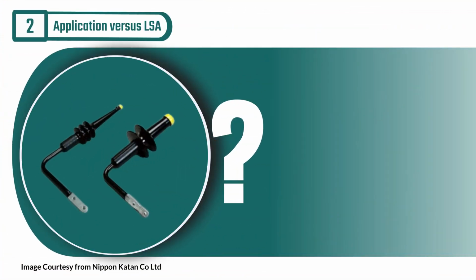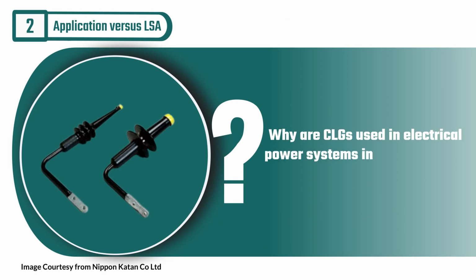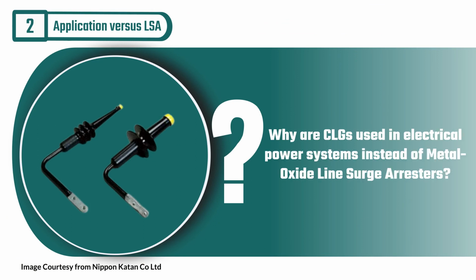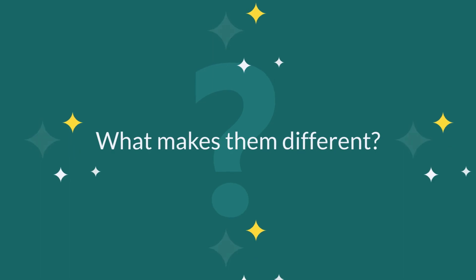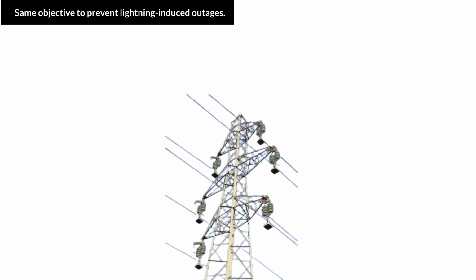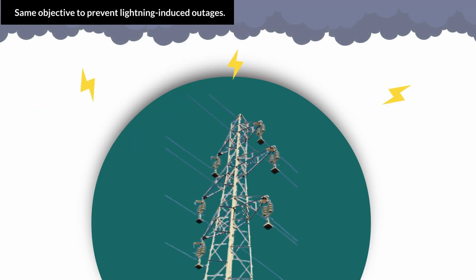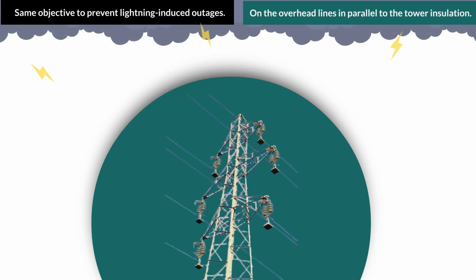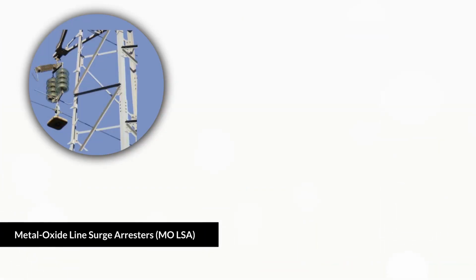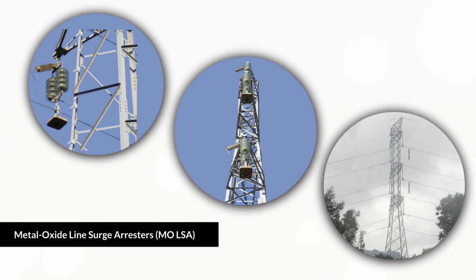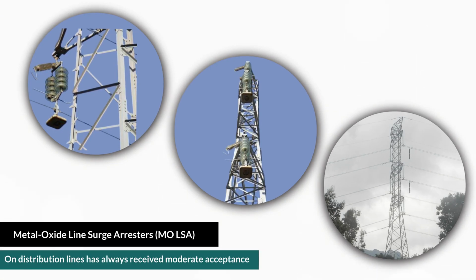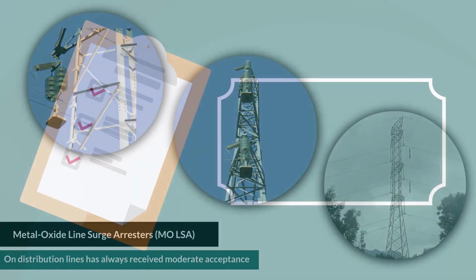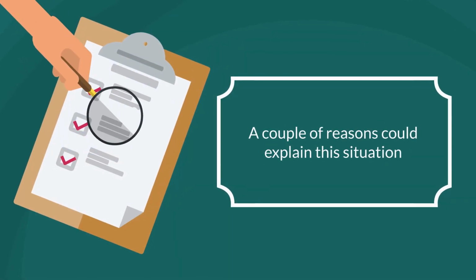Application versus LSA. Why are CLGs used in electrical power systems instead of Metal-Oxide Line Surge Arresters? What makes them different? Line surge arresters, including current limiting gaps, have the same objective: to prevent lightning-induced outages. They are installed on the overhead lines in parallel to the tower insulation. Although Metal-Oxide Line Surge Arresters, MOLSA, are commonly used on transmission lines, their use on distribution lines has always received moderate acceptance. A couple of reasons could explain this situation.